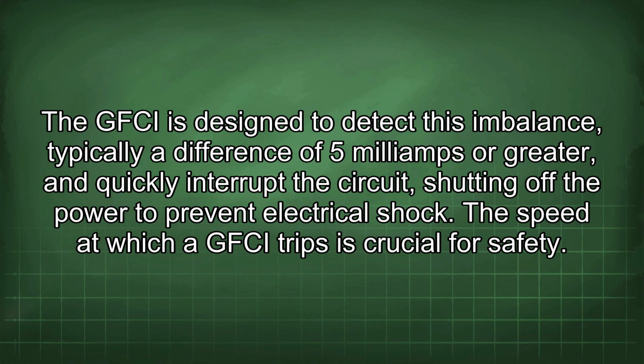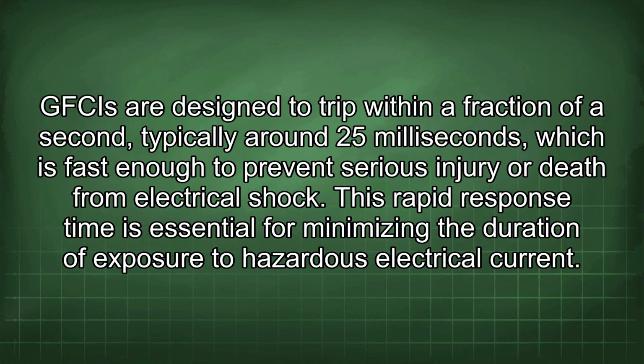The speed at which a GFCI trips is crucial for safety. GFCIs are designed to trip within a fraction of a second, typically around 25 milliseconds, which is fast enough to prevent serious injury or death from electrical shock. This rapid response time is essential for minimizing the duration of exposure to hazardous electrical current.